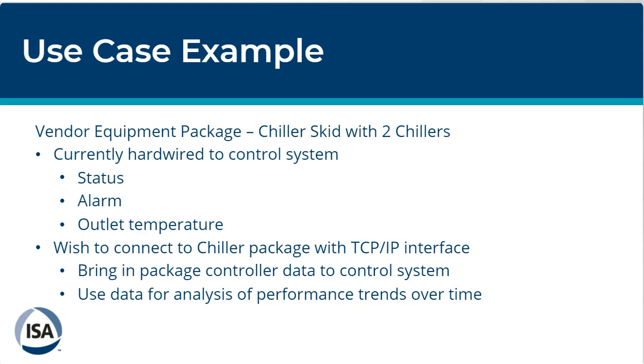So now our digital transformation project is going to look at connecting the chiller package with a TCP/IP interface, bring that controller data back to the control system, and use it for analysis, performance, and trends over time. It may be the lead-lag status, condenser and evaporator pressures and temperatures, hours of runtime, any diagnostic information and trends—the whole purpose may be to improve our predictive maintenance program at the plant.